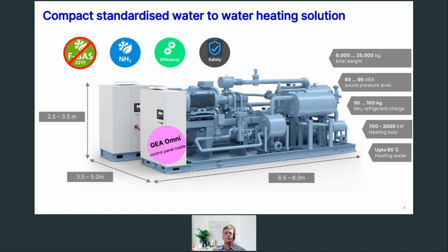First of all, we've introduced this new range of standardized heat pumps, because we've seen for district heating that demand is growing exponentially. To get out there with a standardized solution which improves efficiency and lowers delivery time, we developed this range of heat pumps that can go from low temperatures—ground source, air source, whatever—delivering up to 95 degrees as the hot water outlet. We have a range of different models going from 700 kilowatts up to 3 megawatts.